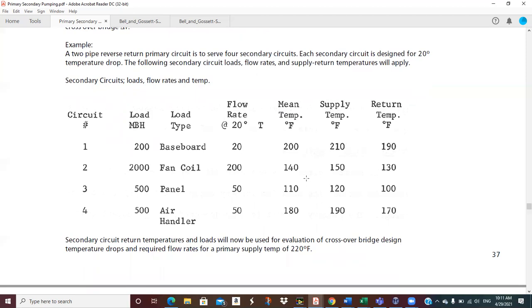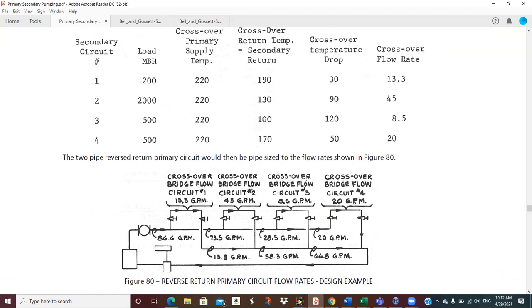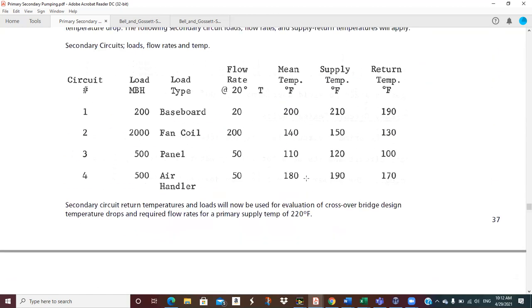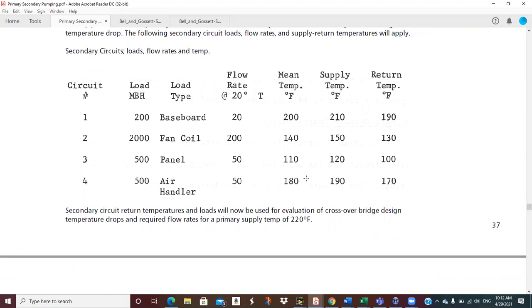So we're going to have a little primary-secondary that we'll see here, and he's given us the numbers for it. For circuit 1, we've run our Carrier program, and it tells me I need 200,000 BTUs an hour for my design heating. I, the engineer, have selected baseboard heating coils, hot water coils, and I've decided on a 20-degree delta T on all of my heating coils. Then I calculate the flow rate at that 20-degree delta T. Well, 200,000 is equal to 500 times GPM times delta T.